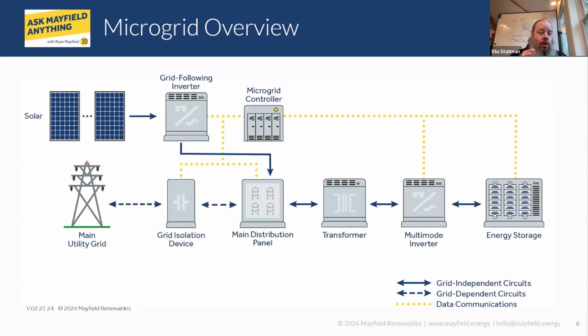We'll have the zero grid export, or zero battery-to-grid export, or the no-charge-battery-from-grid rules baked in there, and respond very quickly - not as quickly as an inverter could, but very quickly - to make sure those rules are followed within the local requirements. The 2-second requirement in California, easily done just by the EMS.